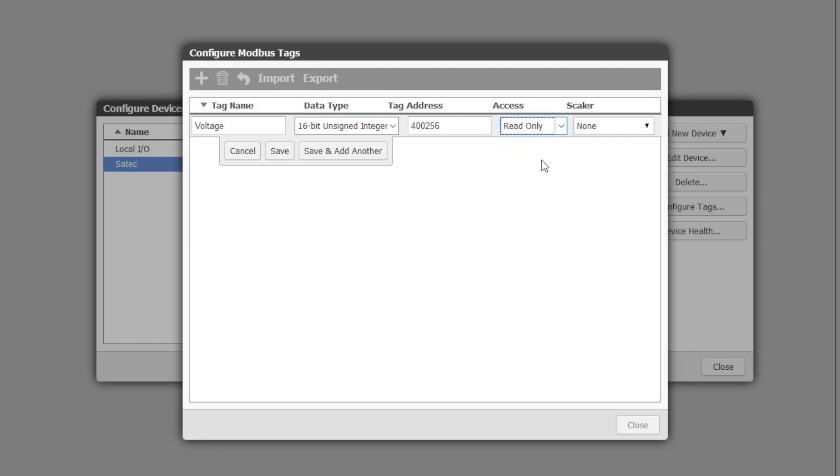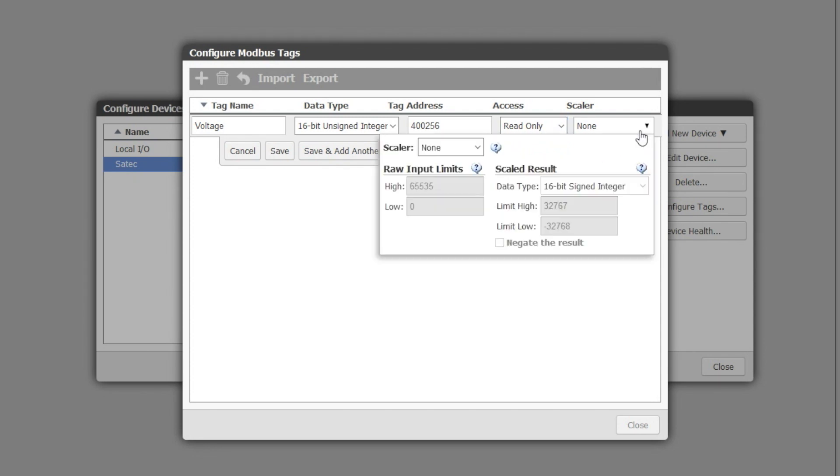And if we just stop here and ran the project we would just see the raw 16-bit number. It would not be very helpful so we need to rescale it into engineering units. In this case volts AC.